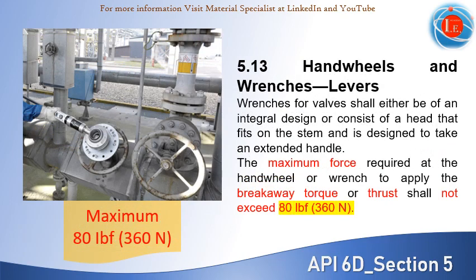Wrenches for valves shall either be of an integral design or consist of a head that fits on the stem and is designed to take an extended handle. The maximum force required to apply the breakaway torque or thrust at the hand wheel or wrench shall not exceed 80 pound-force or 360 newton. The photo in this slide shows a measurement with a torque wrench for verification.